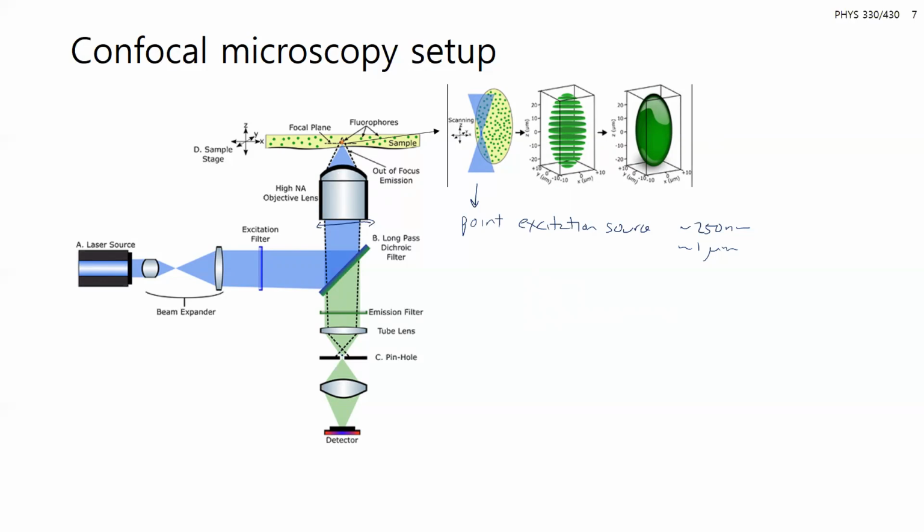That's what the green light is representing here. And you then focus it on a detector. Typically, confocal microscopes have a pinhole, and this was a key development. If you focus your emission light through this pinhole, you can block out-of-focus light and remove any unwanted signal from out-of-focus fluorophores.